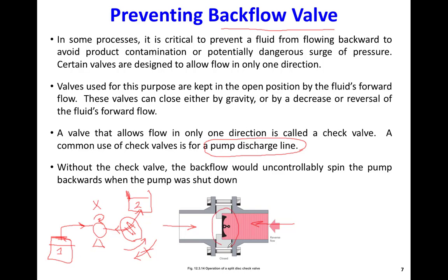This gate in the check valve can work pneumatically or by gravity. For example, if the valve is oriented so the gate is pinned at the top, when there is flow from bottom to top the valve is open. When the flow reverses from top to bottom, the weight of the gate causes it to close due to gravity, blocking the pipeline. This is how a gravity-based check valve works — it is also called a backflow valve.